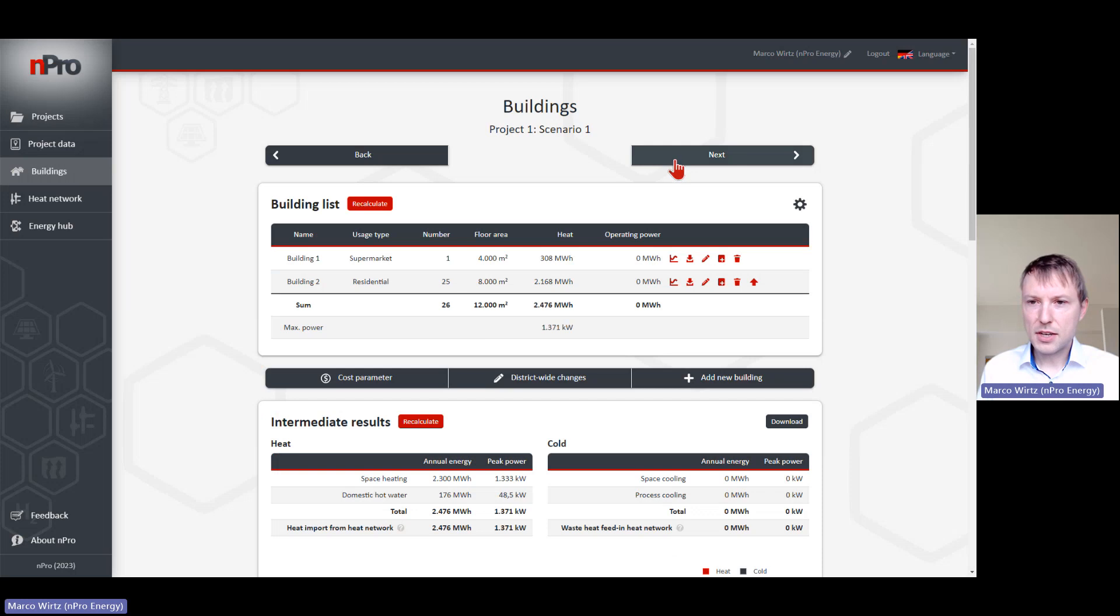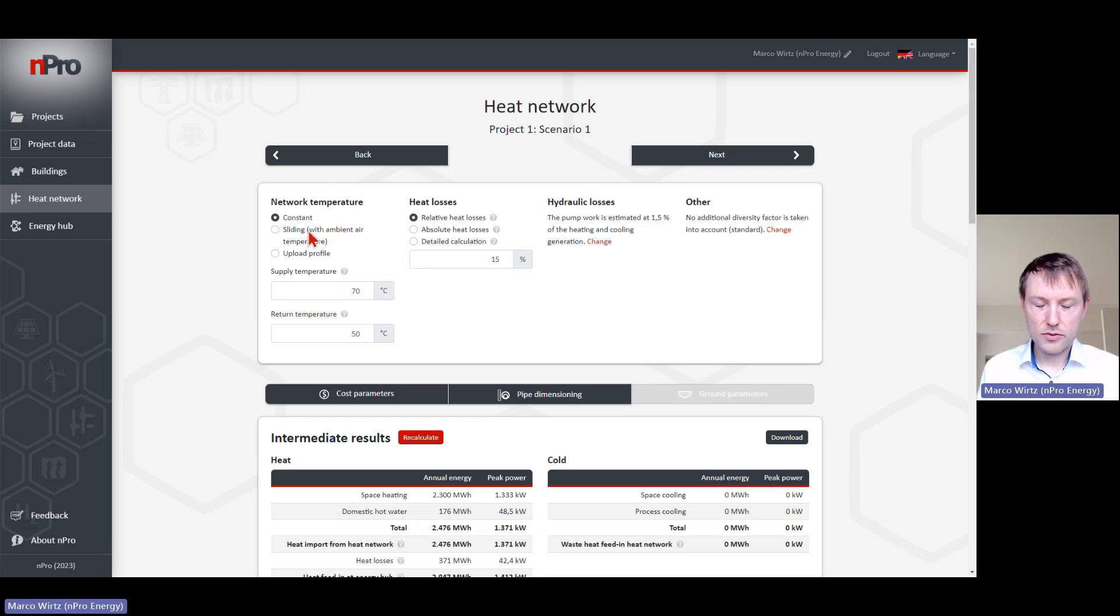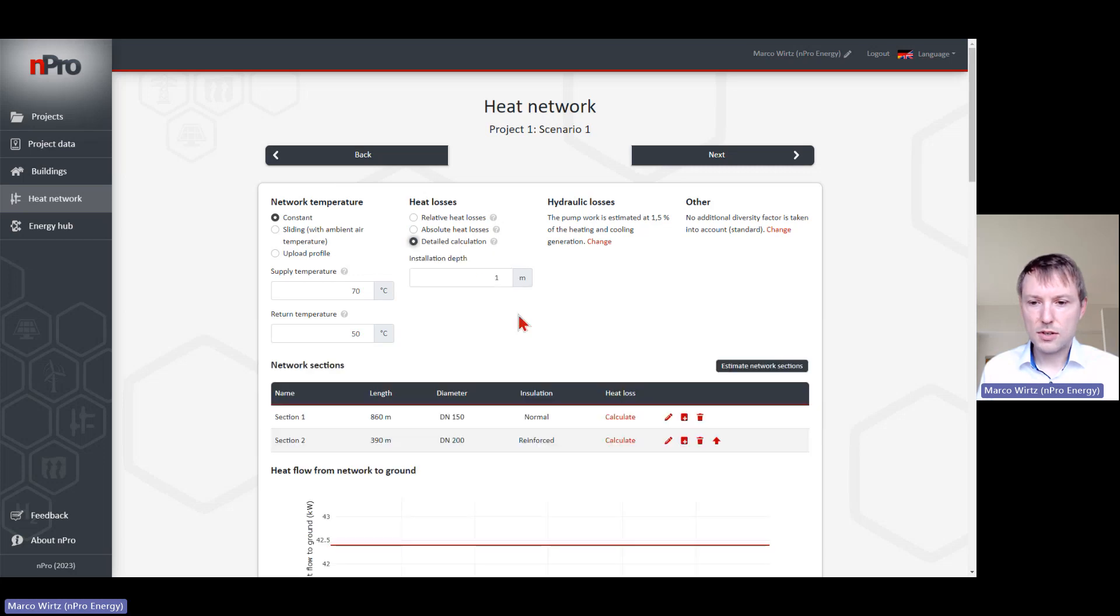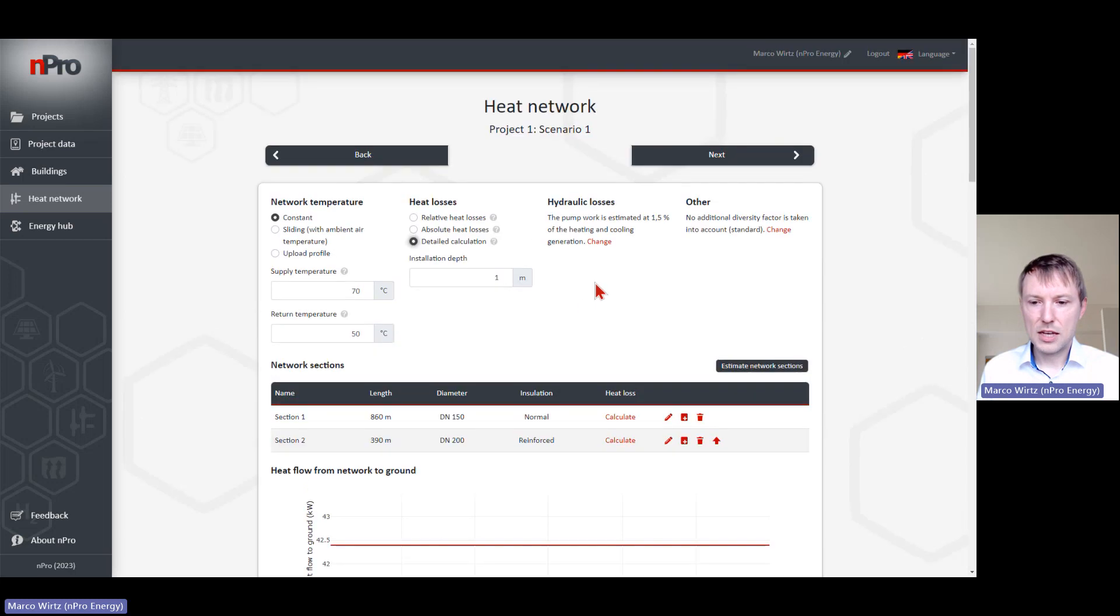On the second page, we find the parameters for the heat network. Which temperature do we have? Maybe a sliding temperature. How do we define the losses? Is it just a loss factor, or do we want a detailed calculation? We can insert different network sections and calculate the losses in detail.